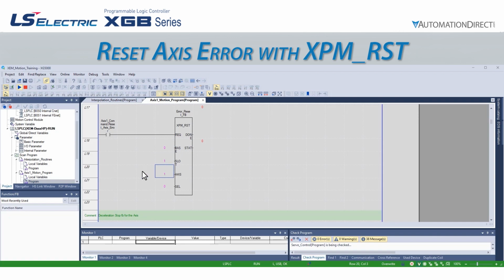The SEL input is a bit value that can be set to true or false depending on whether we wish to attempt to reset common errors or axis errors. In a pulse-trained motion system, this will always be false, as only axis errors are possible. When the reset attempt is complete, the done bit will be true. If no error occurred to the instruction during reset, the stat value will be 0. It is important to note that this status value is for the instruction, not the axis. As we can see, the axis error reset function block is extremely simple and straightforward.